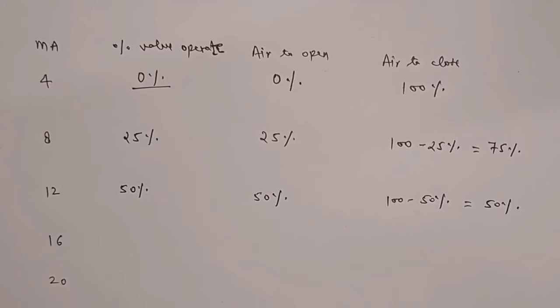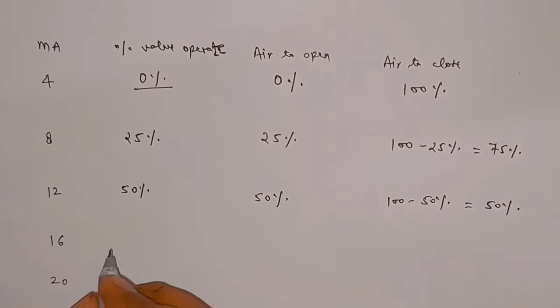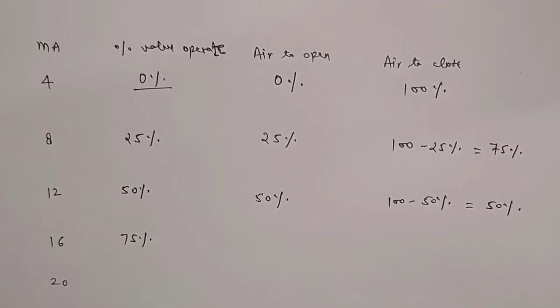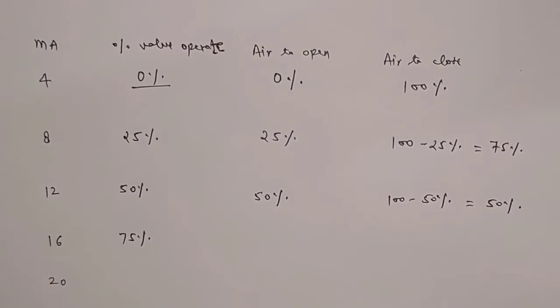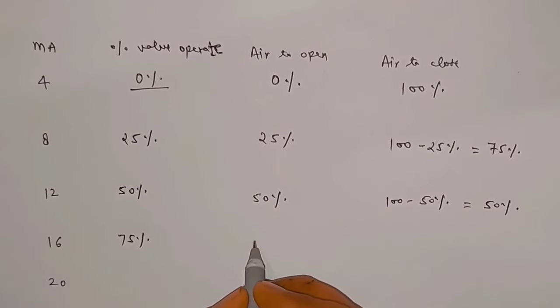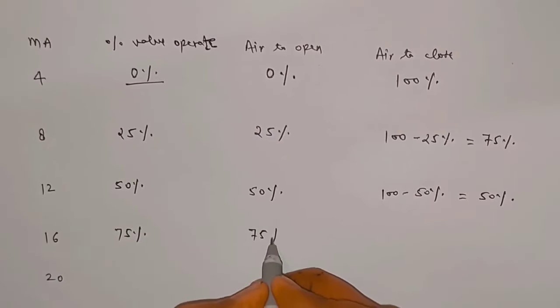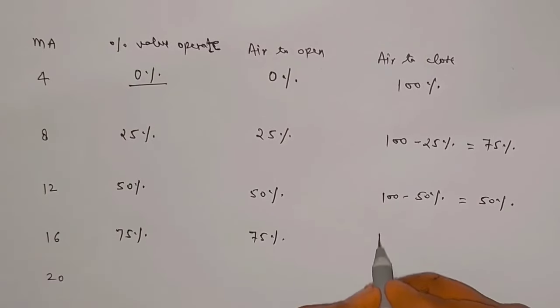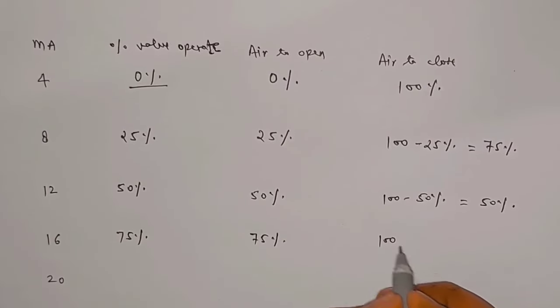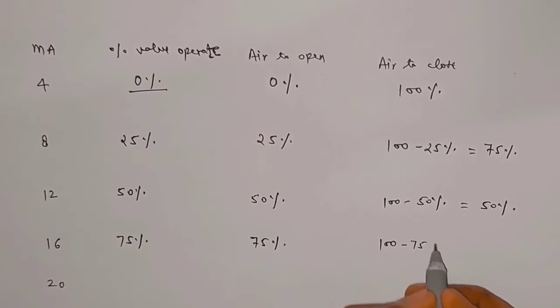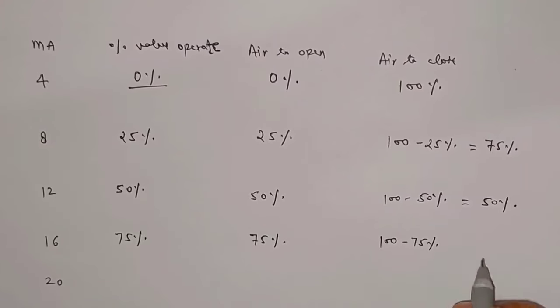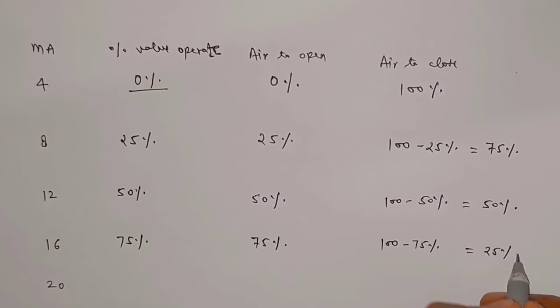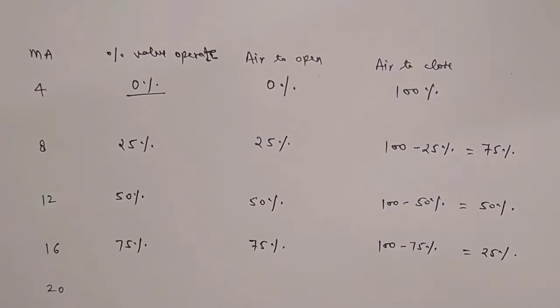Similarly, at 16 milliampere signal, the valve operates at 75%. So the air-to-open control valve opening will be 75%, and the air-to-close control valve opening will be 100 minus 75, so it will come to 25%.